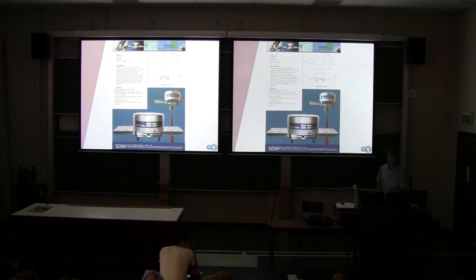And the performance is the same - actually better in a lot of regards. That 0.2% accuracy specification, the de facto standard for conventional CTs, we meet that. But we also have other benefits, like being able to measure all the way down to DC, which a conventional transformer obviously can't do. We can measure DC equally well, and we can measure up to about 50 kilohertz - we could go higher, but the way we set up our sampling system, that's about the limit. A conventional CT starts to roll off around maybe 1 kilohertz if you're lucky, so for power quality measurements and measuring harmonics, this is a far better device.